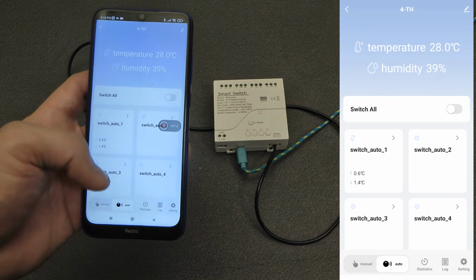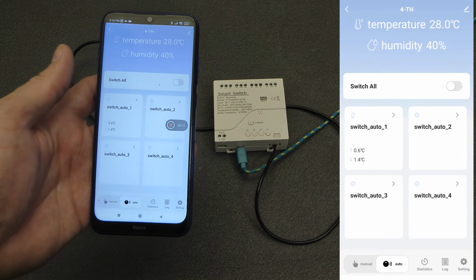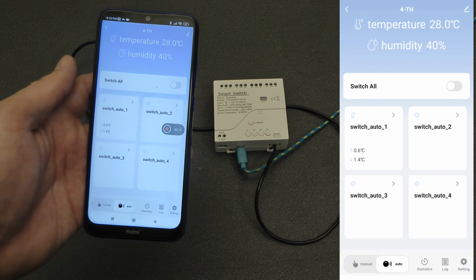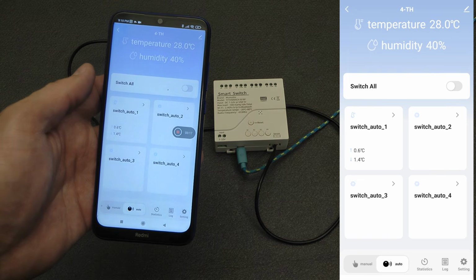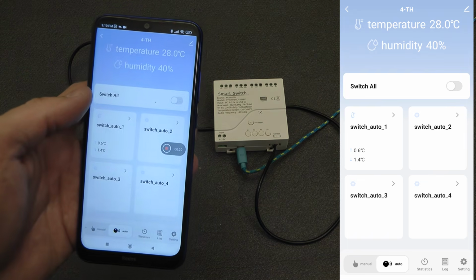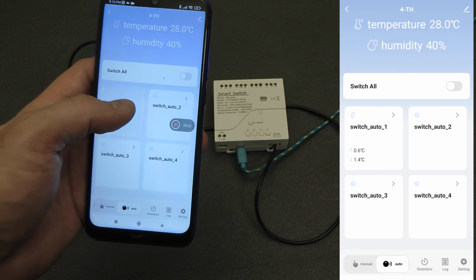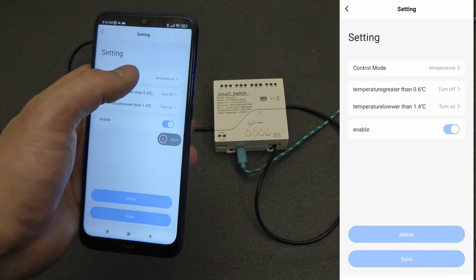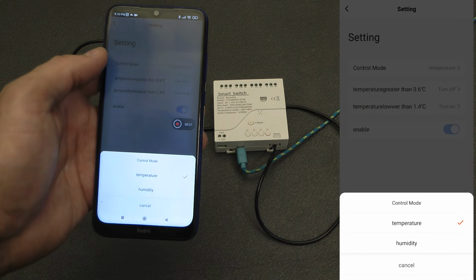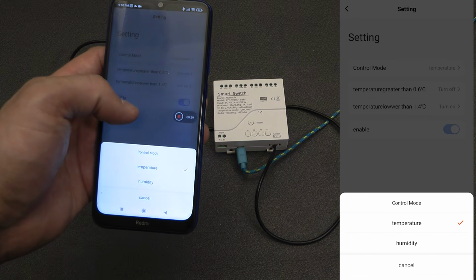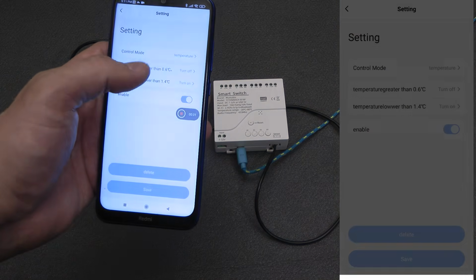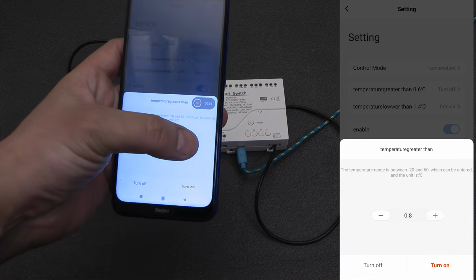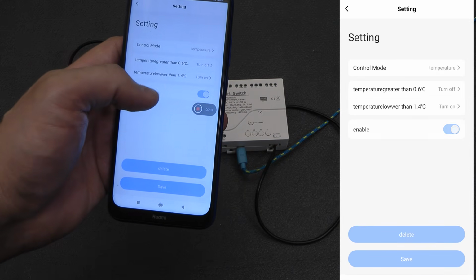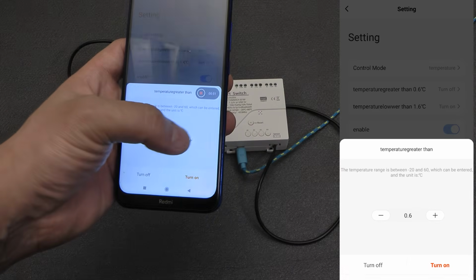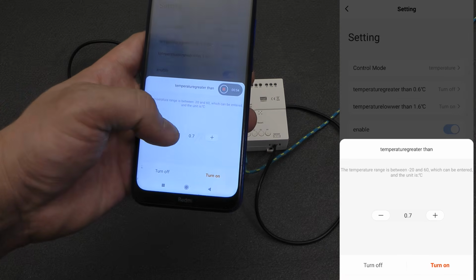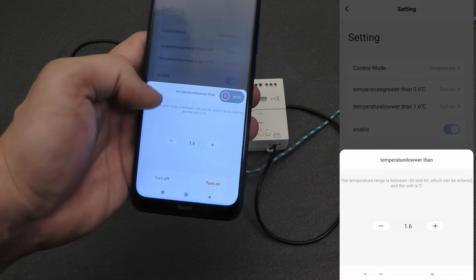For this, there is a separate switch at the bottom of the app. After automatic mode is enabled, the relay can already work autonomously, based on the readings from the external temperature or humidity sensor. We select the required channel, then choose which parameter it should respond to, temperature or humidity. Then we set the condition, greater than or less than the selected value, and choose the action, turn the relay on or off.